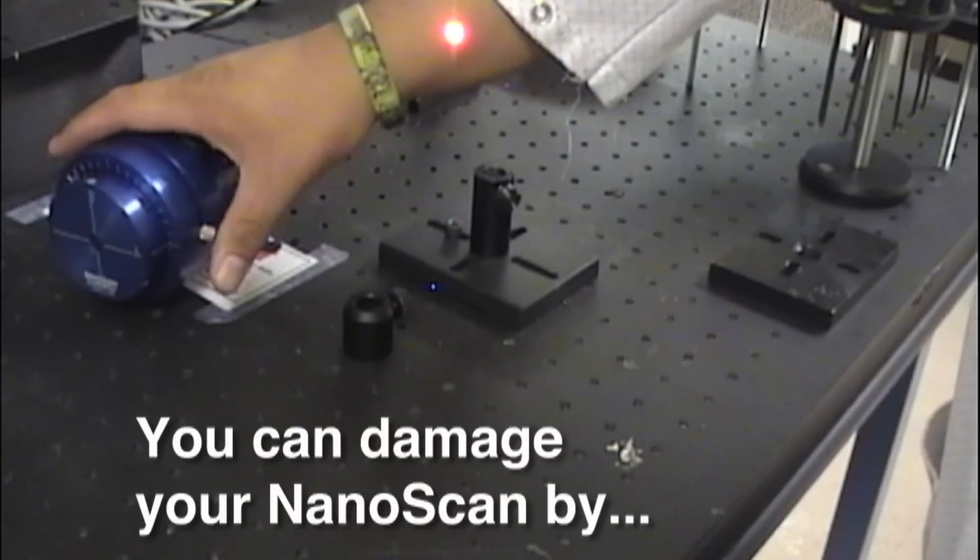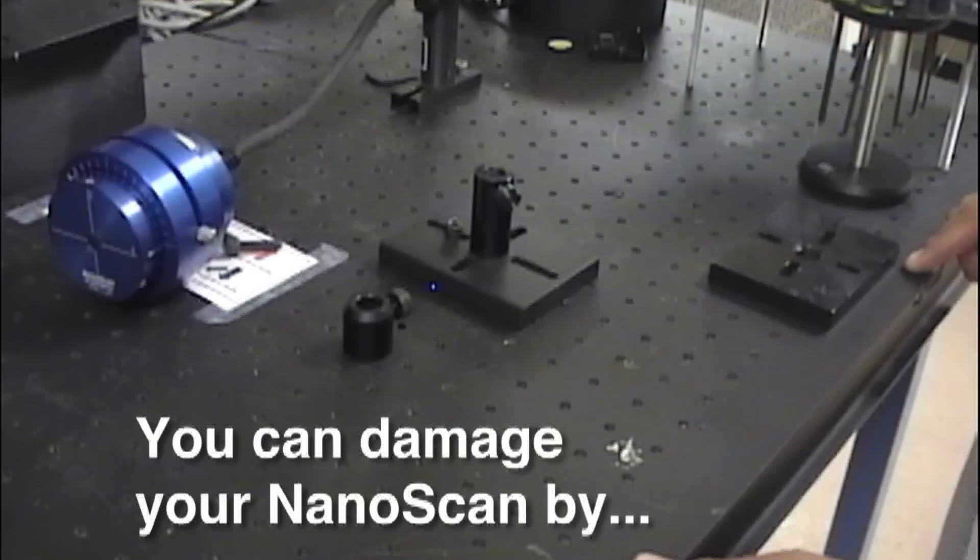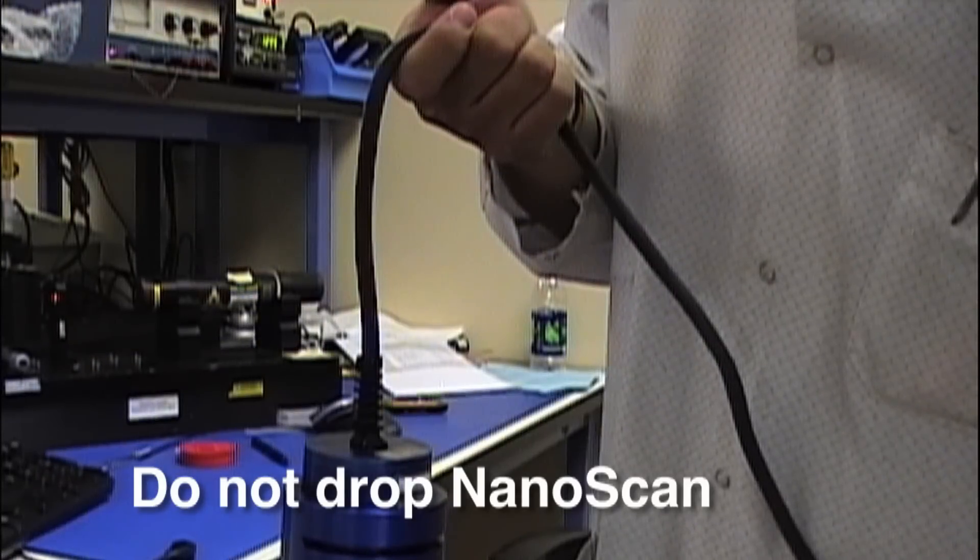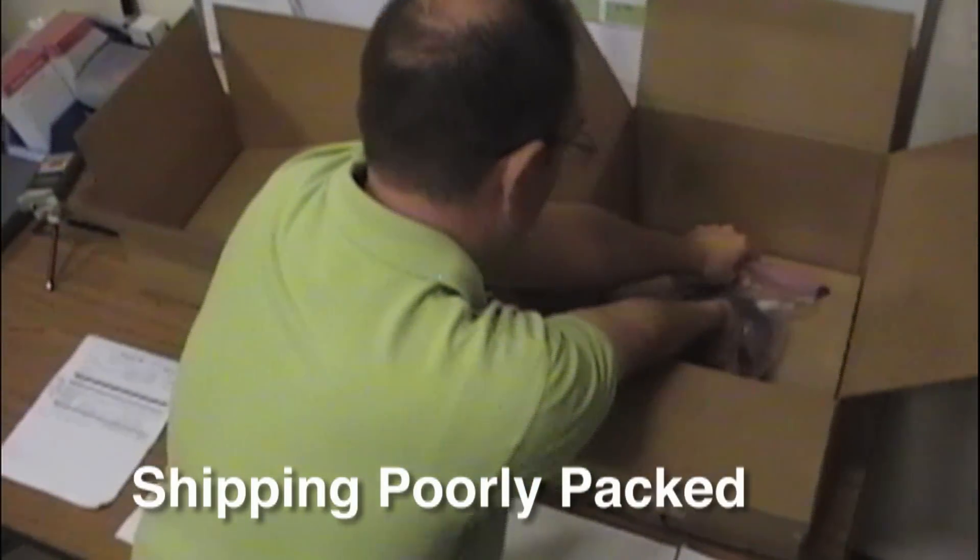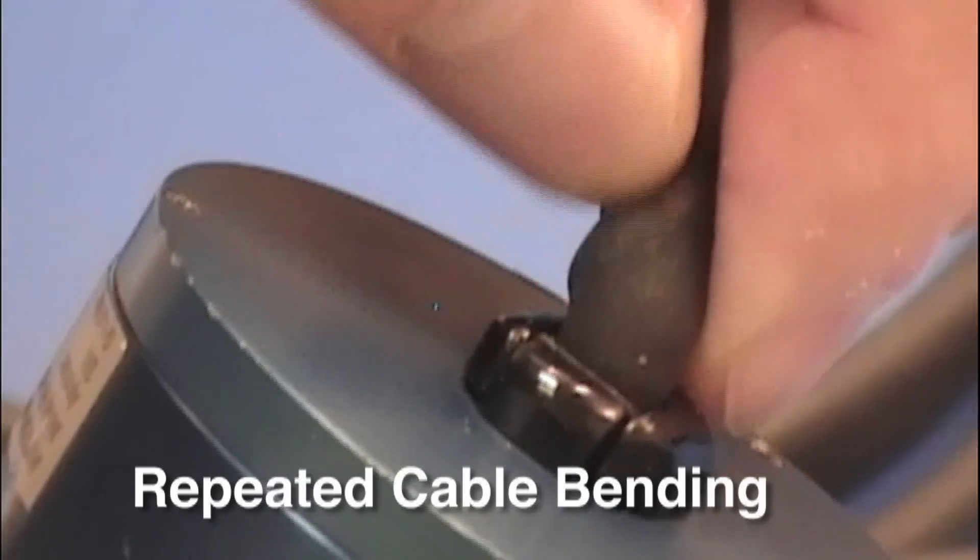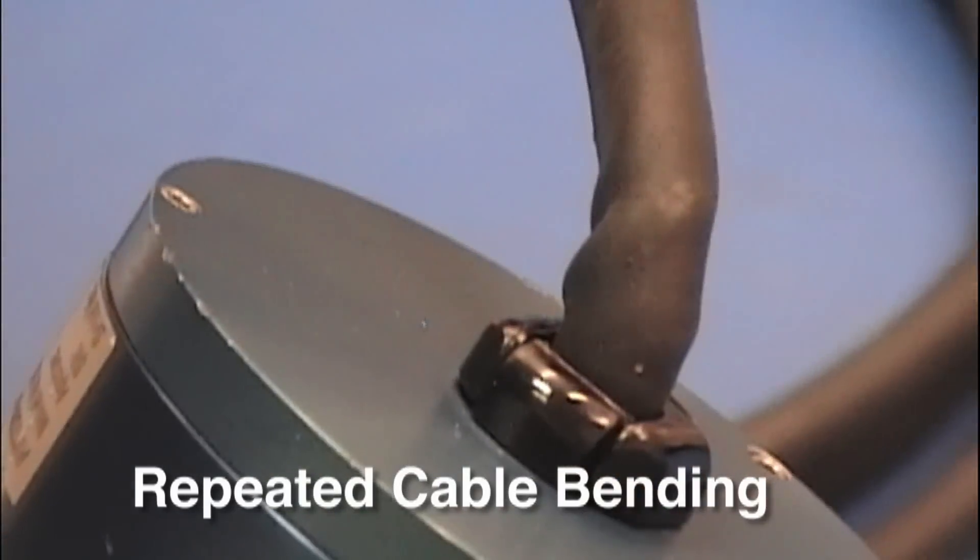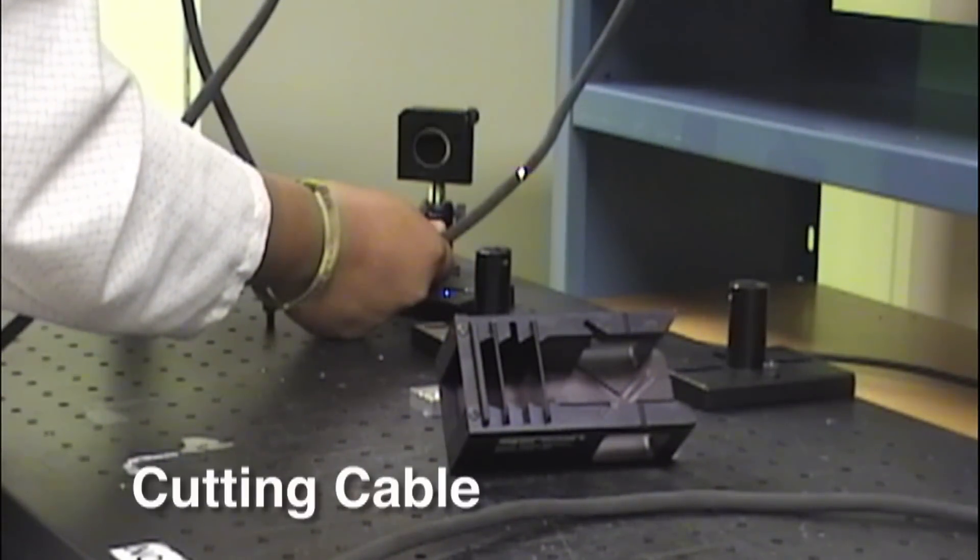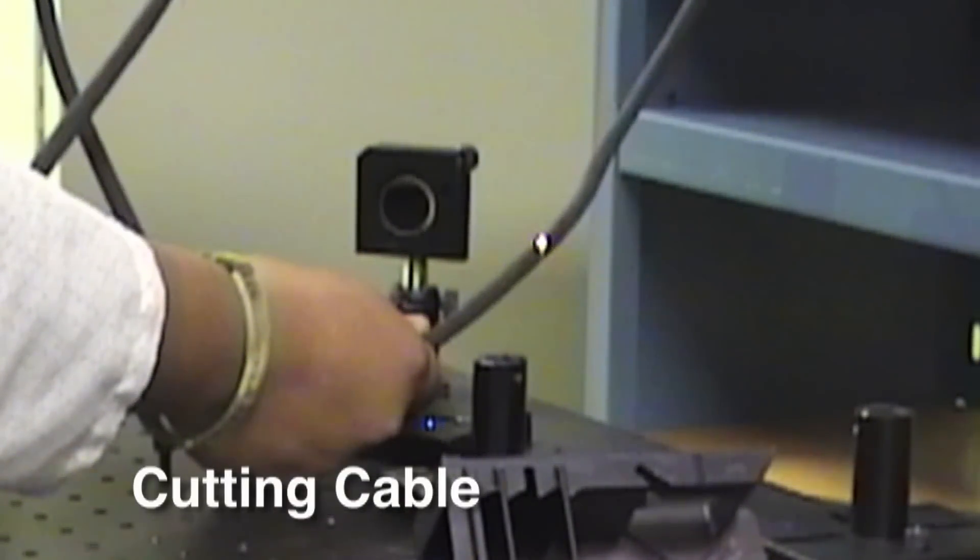You can damage the nanoscan scanning head by dropping it. Do not hold the nanoscan by the cable. Shipping the scan head with insufficient packaging. It can be damaged by bending the cable too tight of a radius or from repetitive bending. Also, the cable can be cut by mechanical means or with high powered lasers.